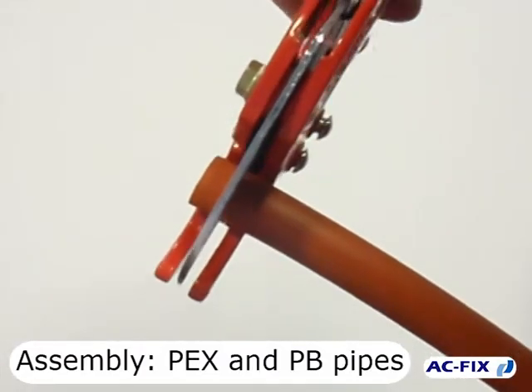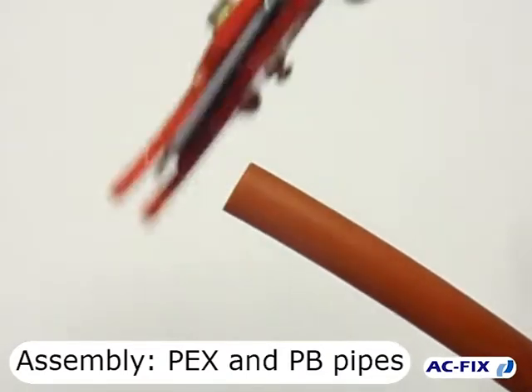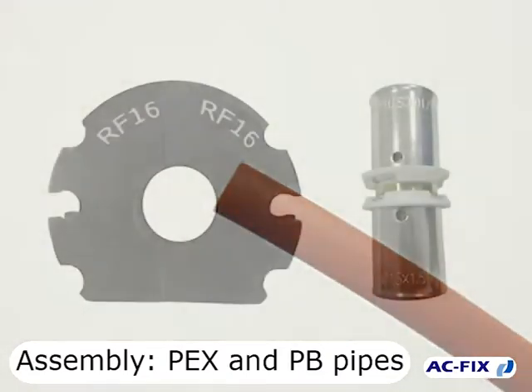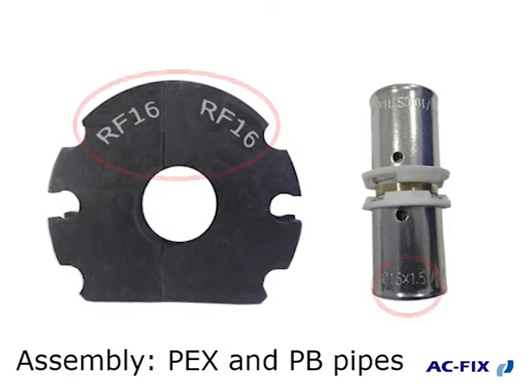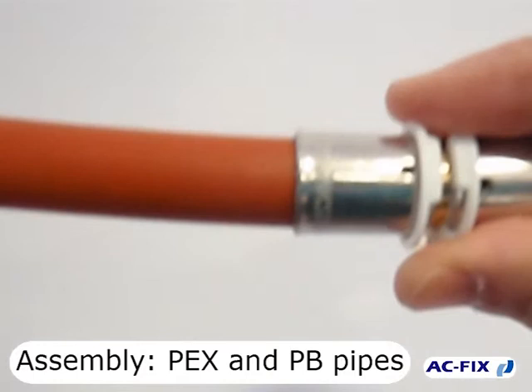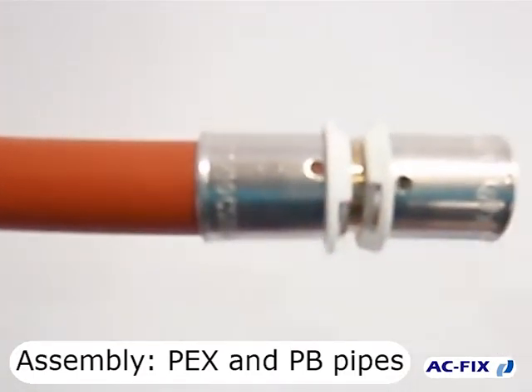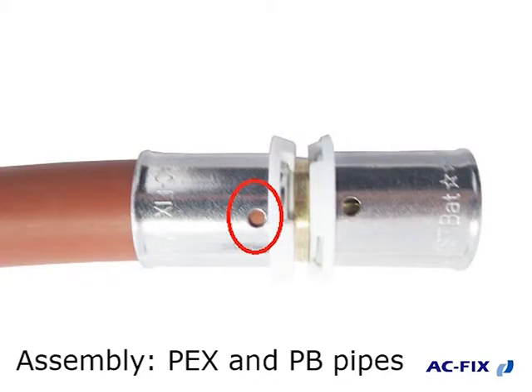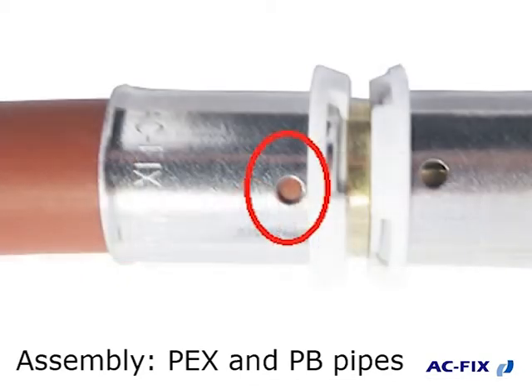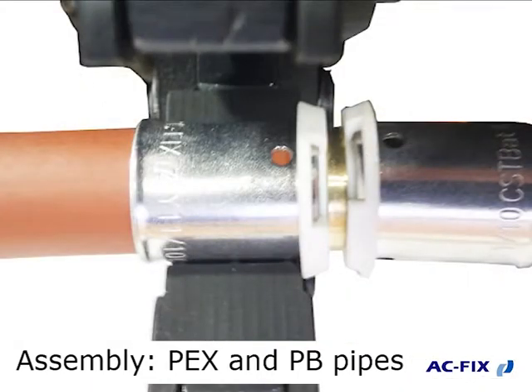Cut the pipe as clean and perpendicular as possible to its axis. Insert the pipe into the fitting — the pipe must cover completely the check holes of the sleeve. Place the side of the jaw beside the plastic part and press.